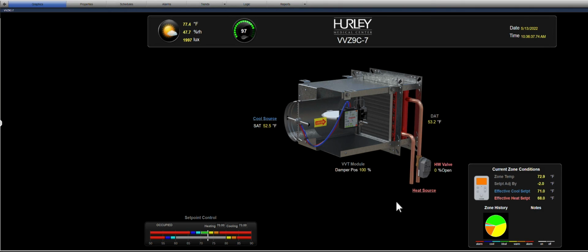But I imagine what we're going to find is that the load between computers and people has changed from the original design. And this is why it probably runs chronically orange. It doesn't get enough cooling BTUs to the space because the space is hotter than what the design is, even though we're compensating with colder air. All right. So that concludes this look at VVZ 9C7 on the 9th floor, nurses station area.